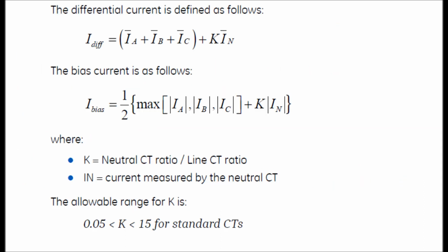The differential current is defined by IDIF equal to the vector sum of all three phase currents plus K into IN. Here IA, IB, IC are the secondary values of the current, and IN is the secondary value of the NCT current. The bias current is defined as I bias equal to half of the maximum value of IA, IB, IC plus K into IN.